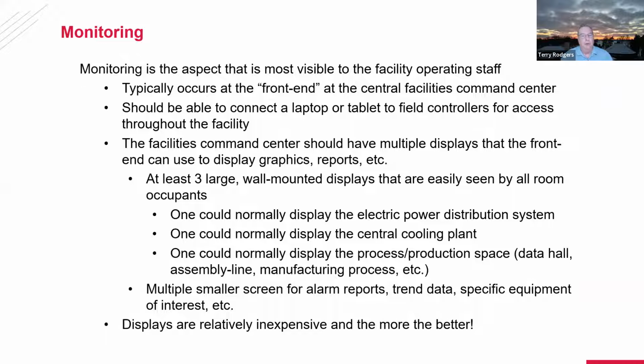Monitoring is probably the most visible aspect of the control systems and the most useful to the facility management staff, since it's assumed the systems are going to control. This is what they use to see how it's being controlled, stability, et cetera, on conditions. It's used to alert the staff of problems, et cetera. So typically, again, you have a front end at the central command center where you can see all of this stuff. But another capability that should be at least considered is the ability to connect laptops up to the field panels so that you can gain insight and be able to view the screens, et cetera, in an equipment room where maybe critical activities are going on.